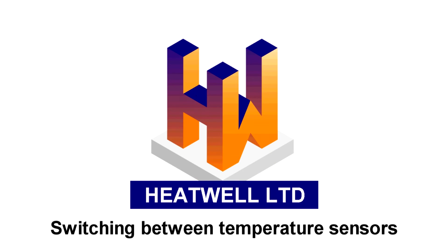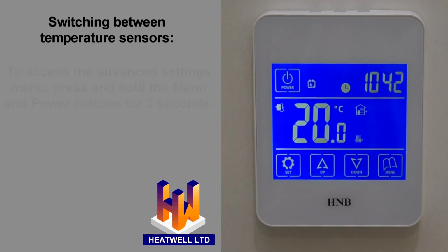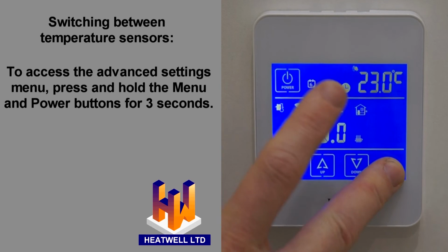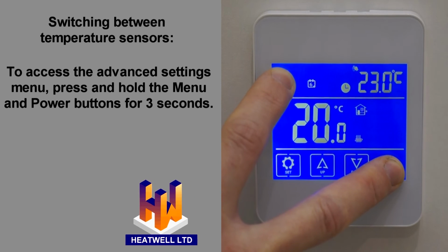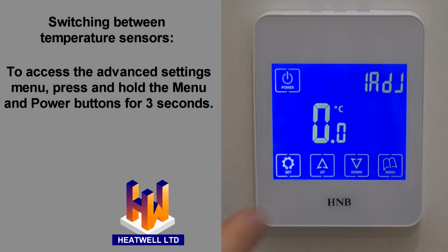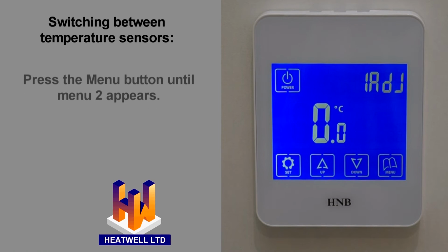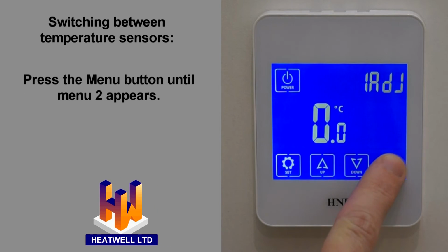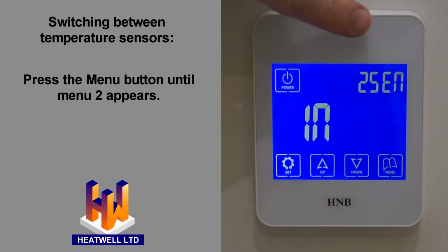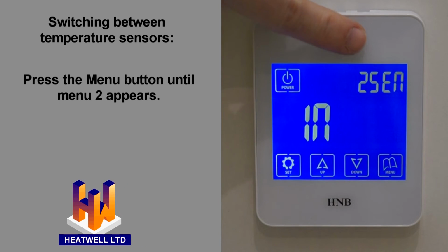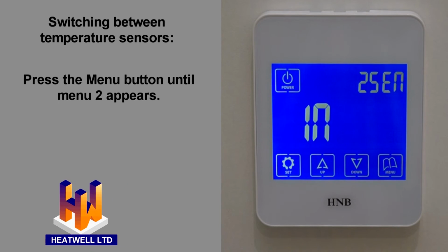Let's move on to advanced settings, starting with switching between temperature sensors. To access the advanced settings menu, press and hold the menu button and power button for 3 seconds. Now we'll select menu number 2 by pressing the menu button 1 time. 2 Sen will appear, which is menu number 2 for changing the temperature sensor.